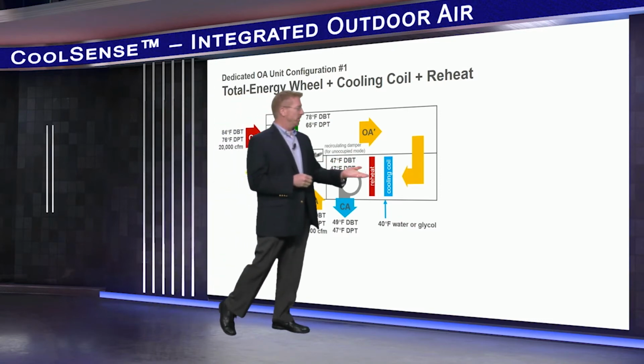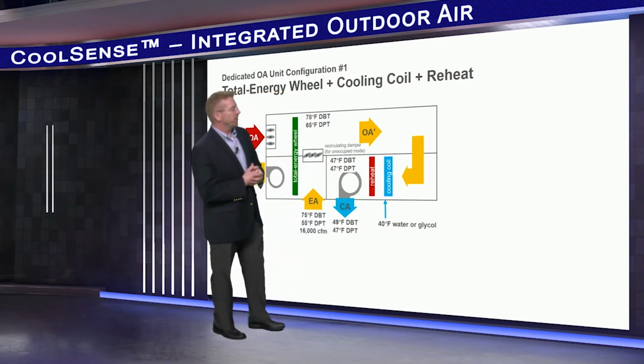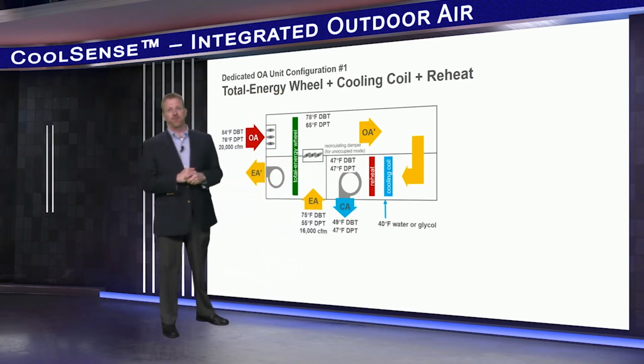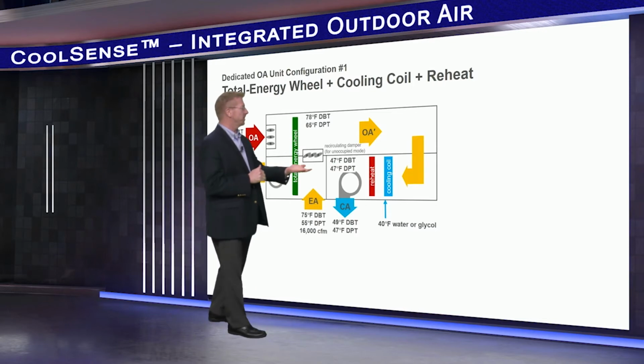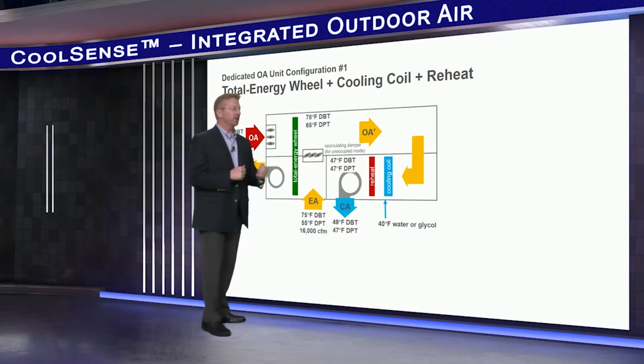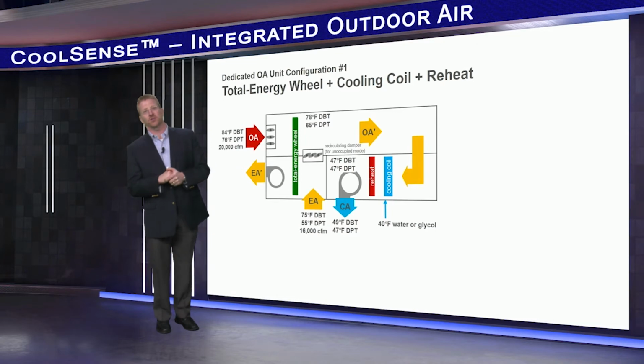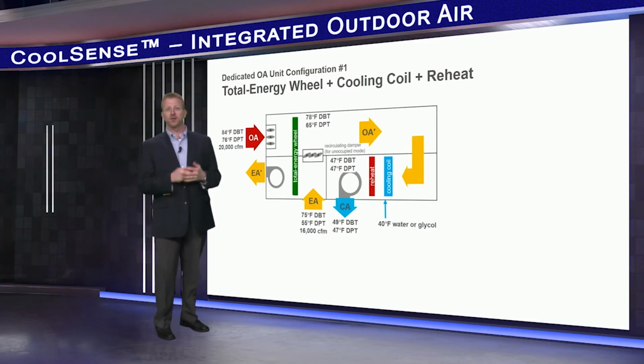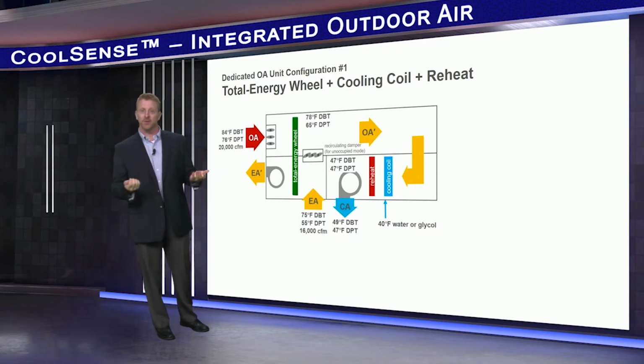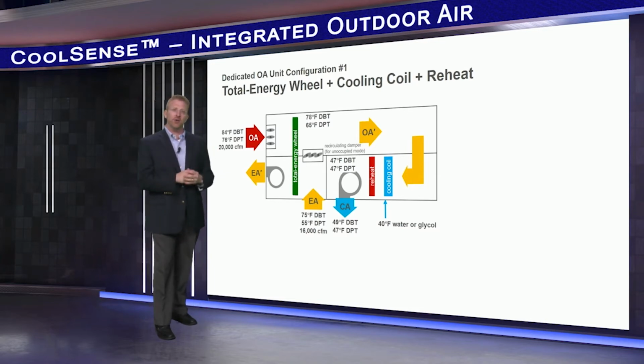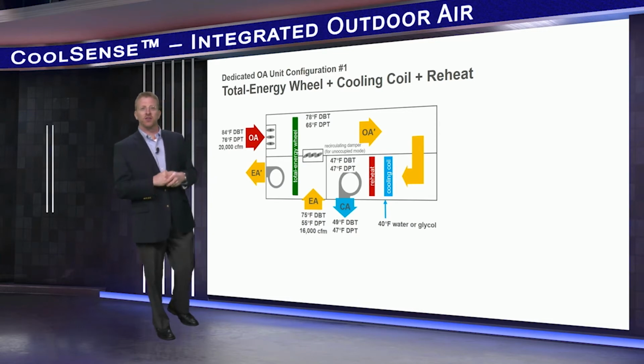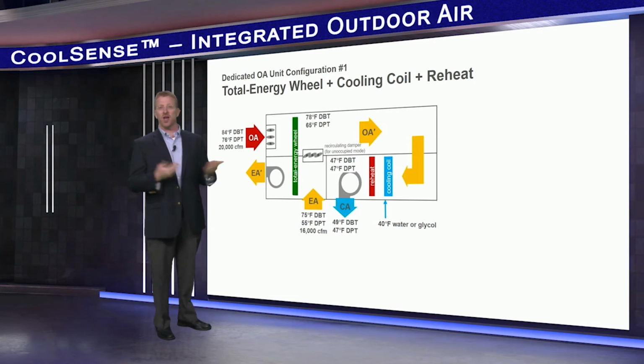Shown here is the cooling coil. As mentioned earlier, this also could be a DX unit. Now look here, the recirculating air damper. This is a key piece that can be seen in all configurations. These dampers can be used for a variety of control strategies, including the morning dry out mode I mentioned earlier. By closing the outdoor air dampers and opening these recirculating dampers, this changes the DOAS unit into a giant dehumidifier that dries out recirculated air if necessary to lower the dew point.